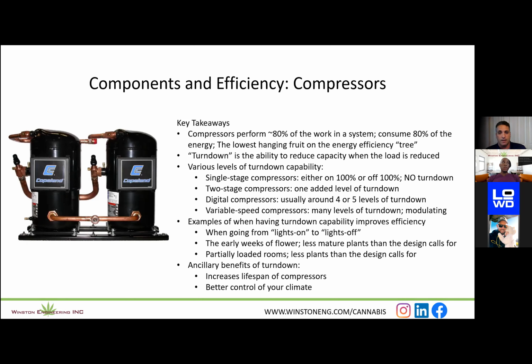Many of the heartburn stories I've heard in this industry are that clients can't control the space. They're all over the place on their temperature and humidity. Then we'll find out that they've got a single stage compressor. As soon as that compressor turns on, you're at 100% of that capacity. You may only be 50% loaded in the space. So that compressor is going to turn on and turn off really quick, right?